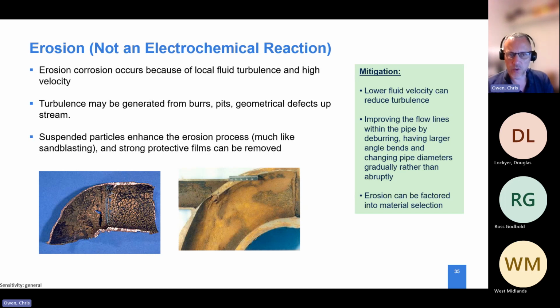And of course, when you've got changes in geometry, or as we can see here, a bend where the turbulence may be almost shot blasting that debris into the side of the wall, you end up with a thinning of that wall, which becomes an area of weakness, and pitting takes place. Then depending on your pressure, you can end up with that wall breaking through.